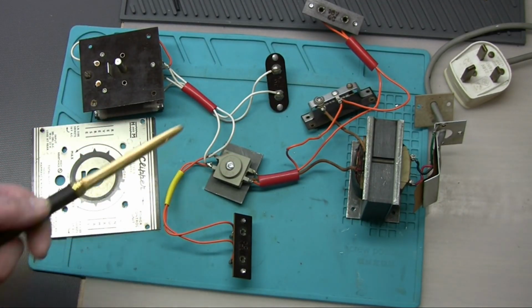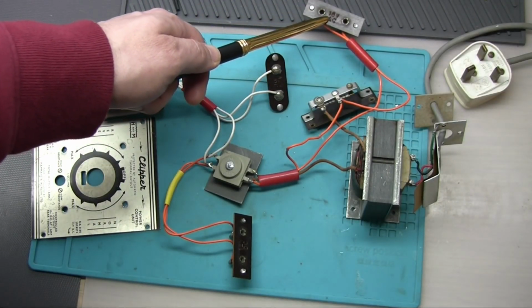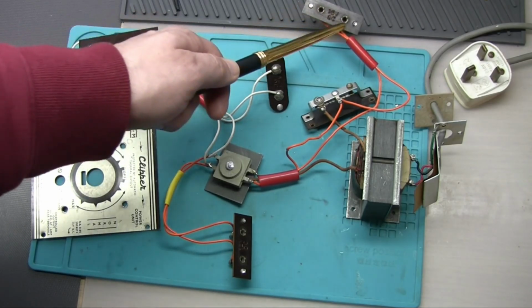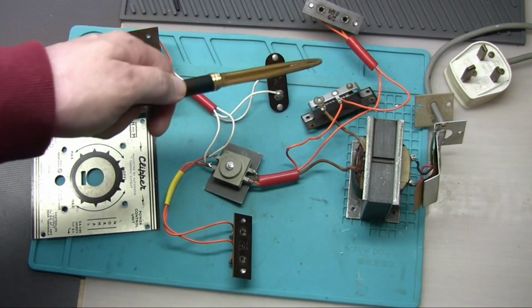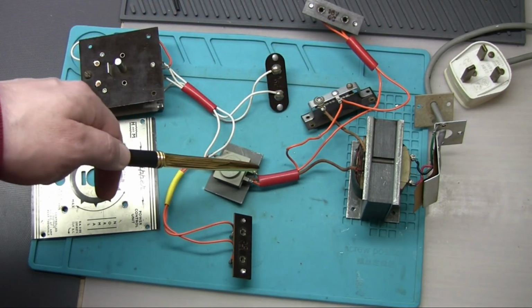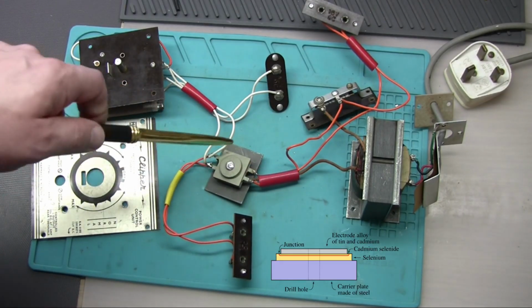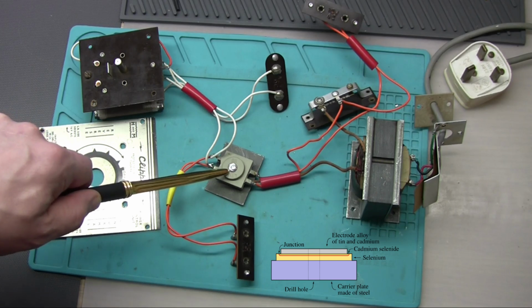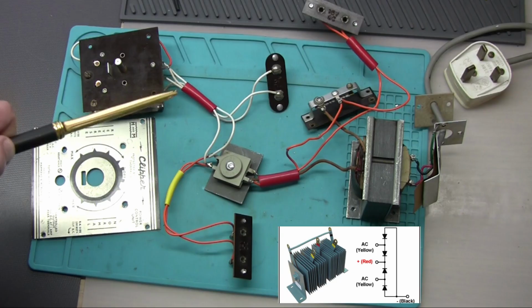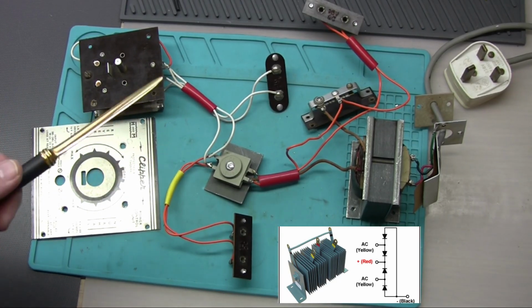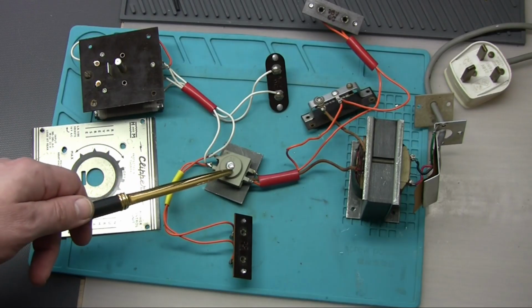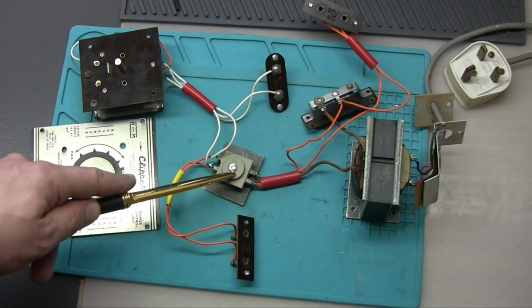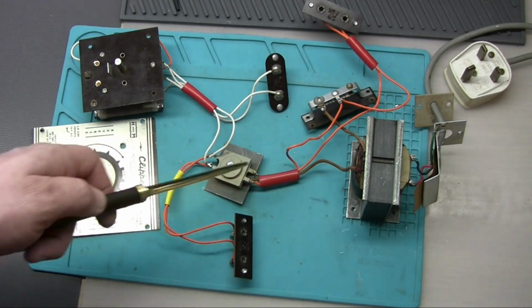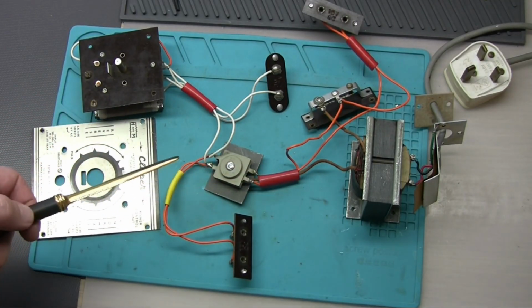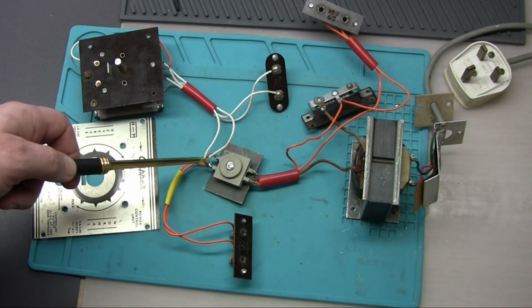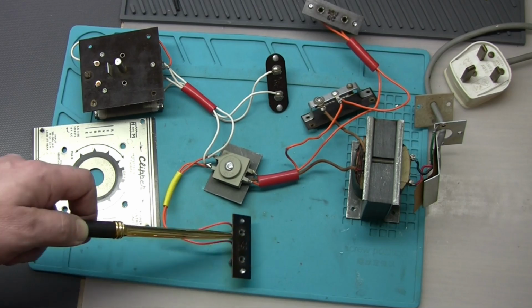Then we have AC current coming out here, which also goes into this selenium rectifier bridge. That gives away the age of this design, because selenium bridges were invented in 1933, and were replaced by more modern silicon rectifiers in the 1960s. So this is likely from the 1950s-1960s. The rectified DC current from this point goes into these contacts.